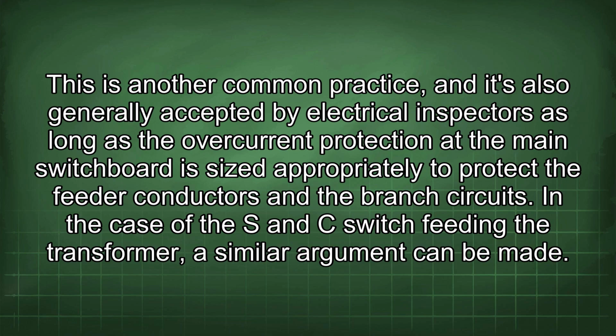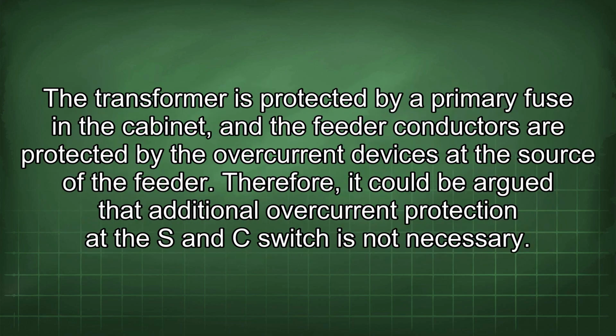In the case of the S and C switch feeding the transformer, a similar argument can be made. The transformer is protected by a primary fuse in the cabinet, and the feeder conductors are protected by the overcurrent devices at the source of the feeder. Therefore, it could be argued that additional overcurrent protection at the S and C switch is not necessary.